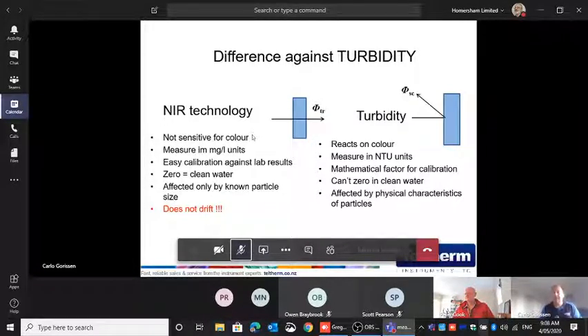Clean water for us is zero. So you put it in a glass of water, it should be zero. Very easy. You normally don't have to do that with commissioning, but after a few years, we always tell people to once in a while check it in clean water, because you could have fouling on the sensor, on the surface of the glass. And then, of course, your zero is off. But it's very easy to see that.